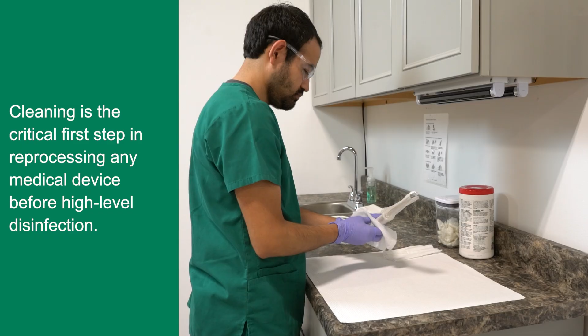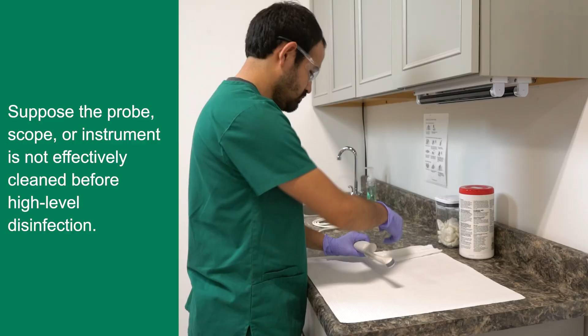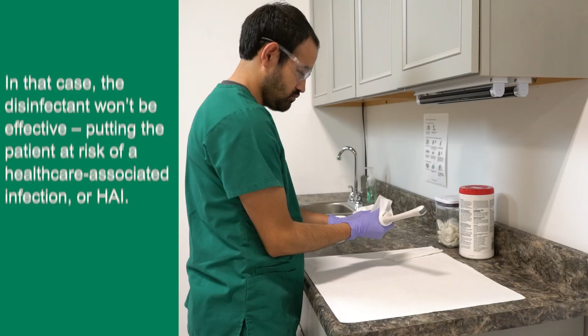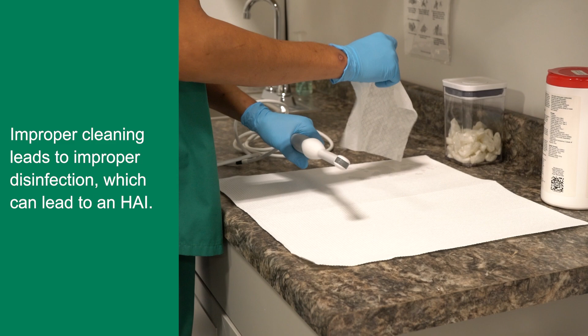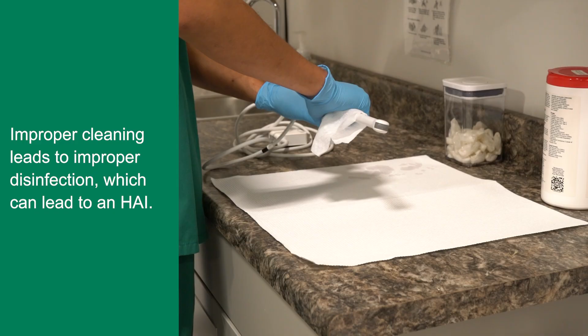Cleaning is the critical first step in reprocessing any medical device before high-level disinfection. Suppose the probe, scope, or instrument is not effectively cleaned before high-level disinfection. In that case, the disinfectant won't be effective, putting the patient at risk of a healthcare-associated infection, or HAI. Improper cleaning leads to improper disinfection, which can lead to an HAI.